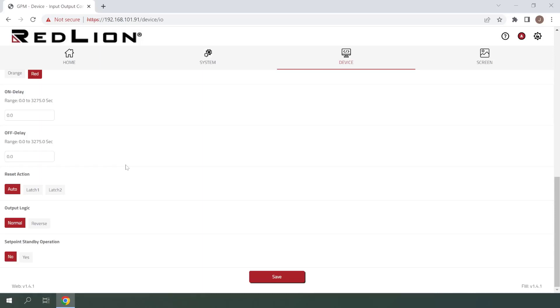The final setting here is Setpoint Standby Operation. When set to Yes, the alarm is disabled after a power-up until the trigger point is crossed. For this example, I'll be leaving this set to No. At this point, we can click Save and navigate to the Home page to test our newly configured setpoint alarm.